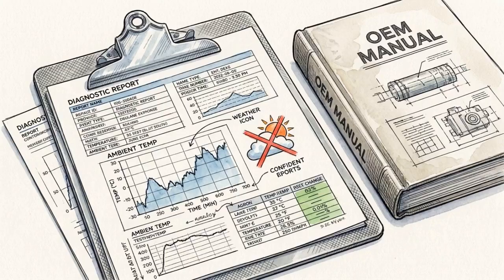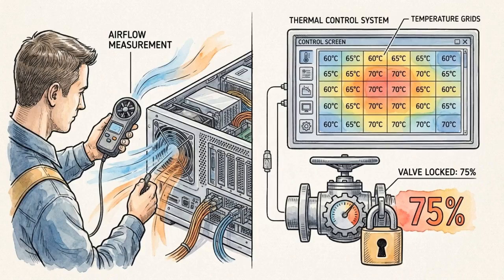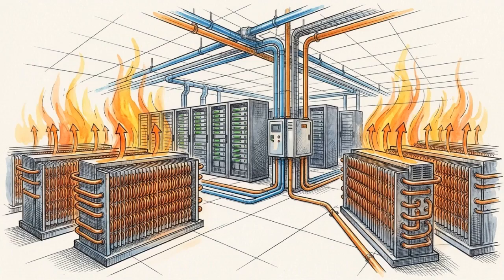Entering the blue gate for functional performance testing, we strictly reject linear ambient weather corrections. All field data must be normalized using approved OEM and AHRI methods. CRAH validation requires the simultaneous capture of airflow, delta T, and valve position. Recording these independently invalidates the test by masking dangerous bypass routes. We then introduce heat load testing.